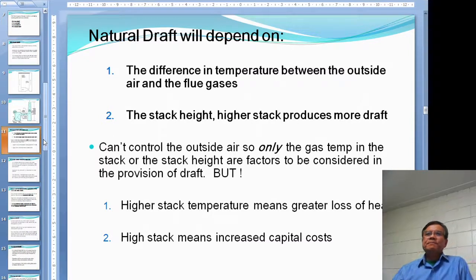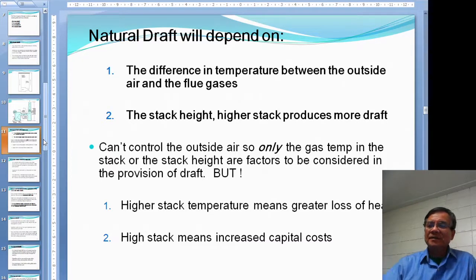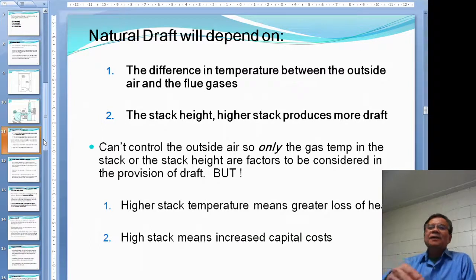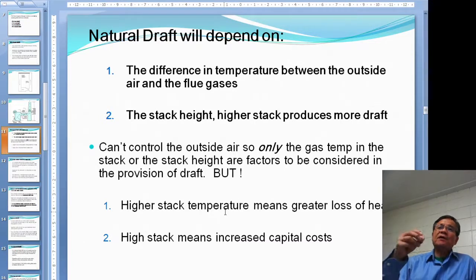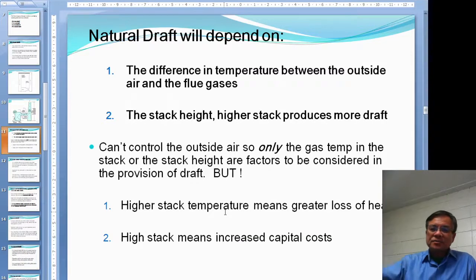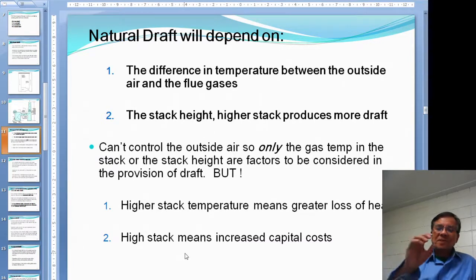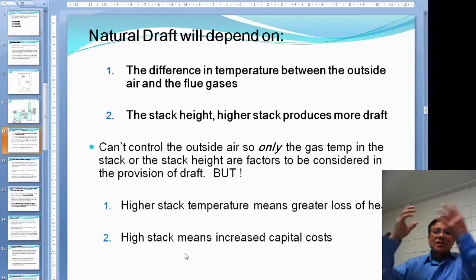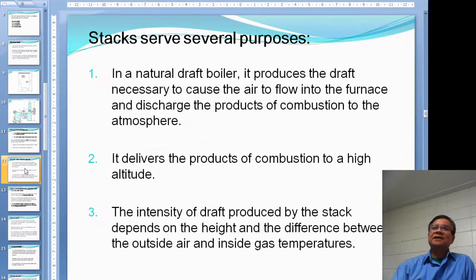We have no control of the weather outside, but we do have control of the temperature inside the chimney. If you burn more fuel, the flue gas will be hotter and the draft will be better. But the problem is, if you have a higher temperature in the flue gas, you are not recovering all the heat — the heat just goes out the chimney and you lose money. Another way to increase draft is a taller chimney, but there is only so much you can do. At some point the capital cost becomes too high, so you have to balance cost against draft performance.